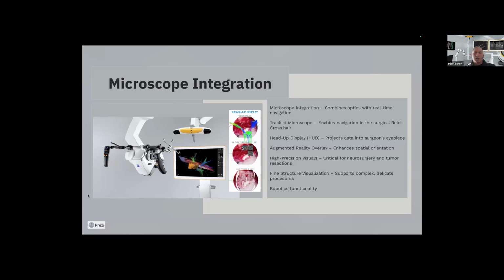Some other functionality that you also see in the microscope is stuff like the robotics function. So technically we can have a head in front of us. We could take our navigation pointer if the microscope was close enough, because obviously the robotics function only drives the head in its aiming movement. It doesn't drive the head into the theater environment, but technically you could click on something and save it with the navigation pointer, and then click the function on the microscope and tell it to look and focus at the point you just touched, or we could actually get the microscope to follow a point in space.